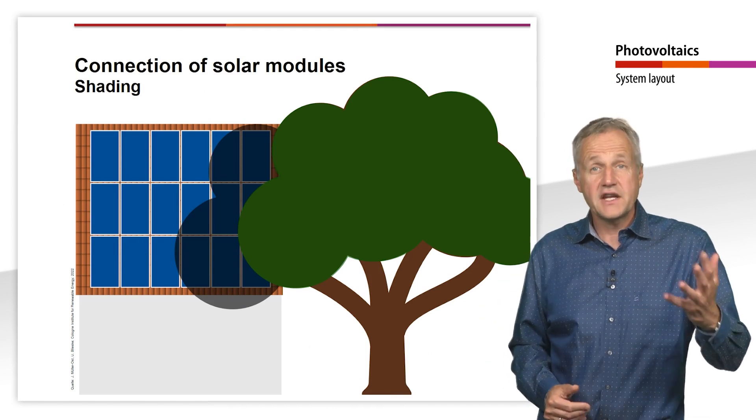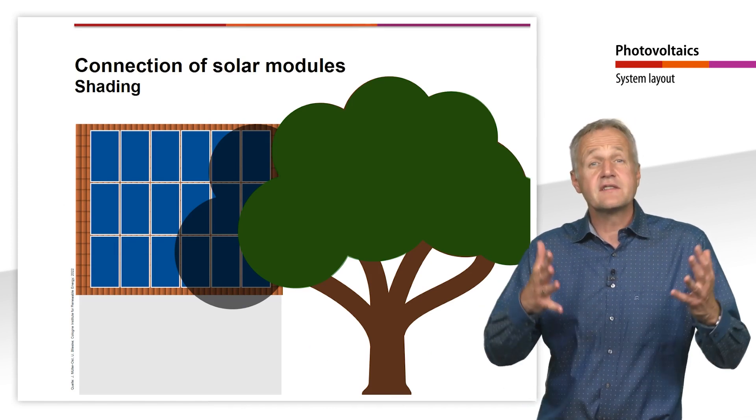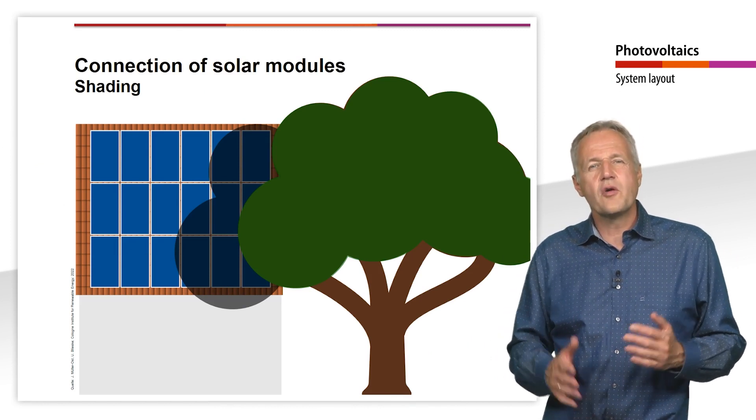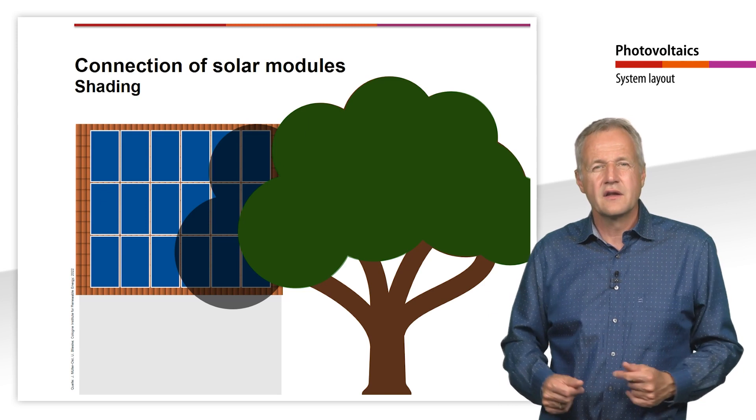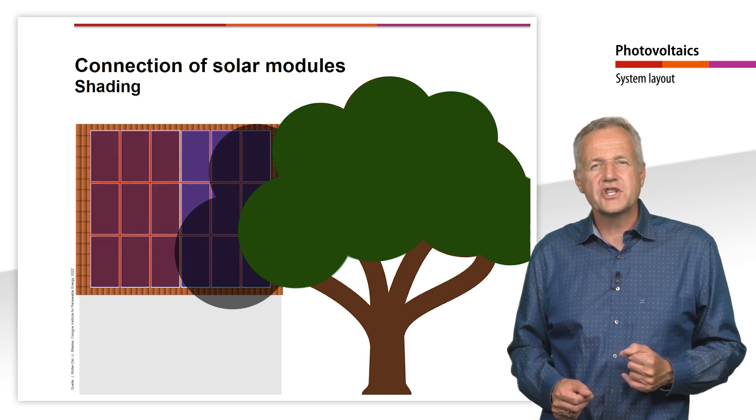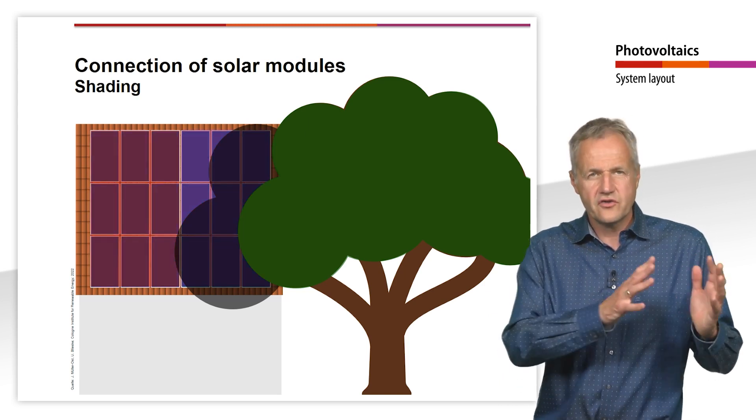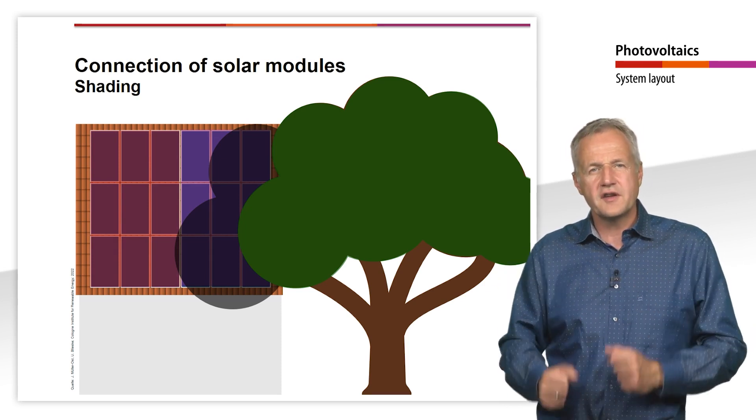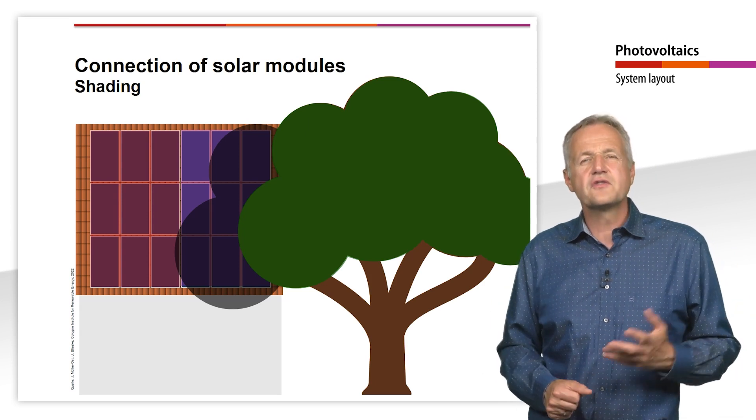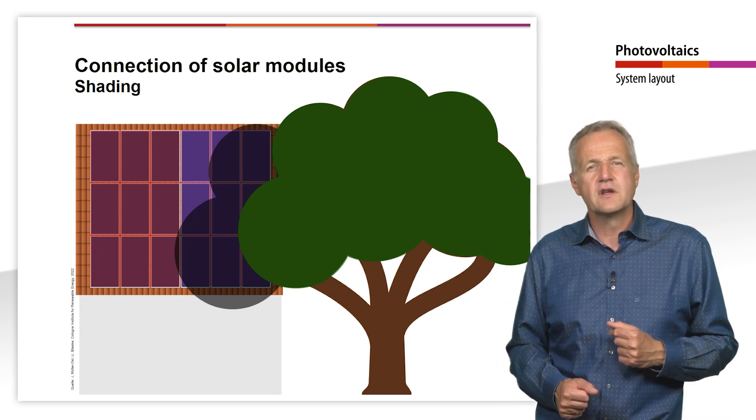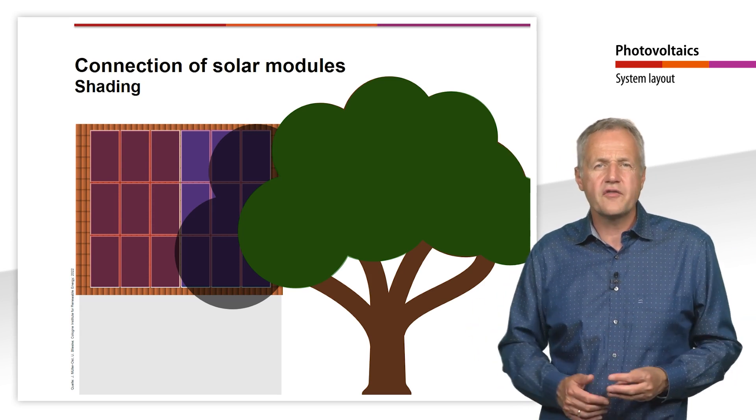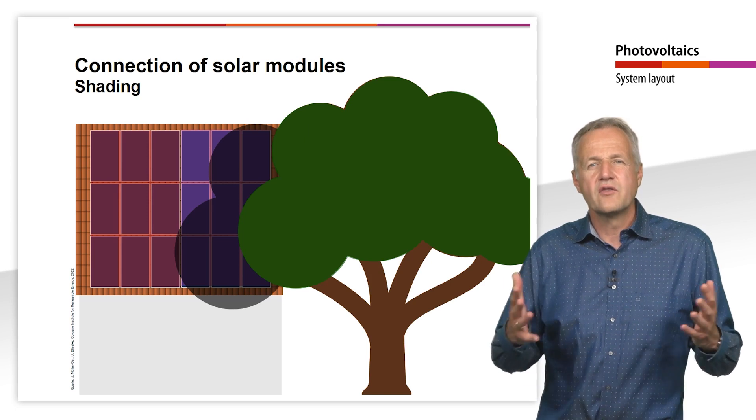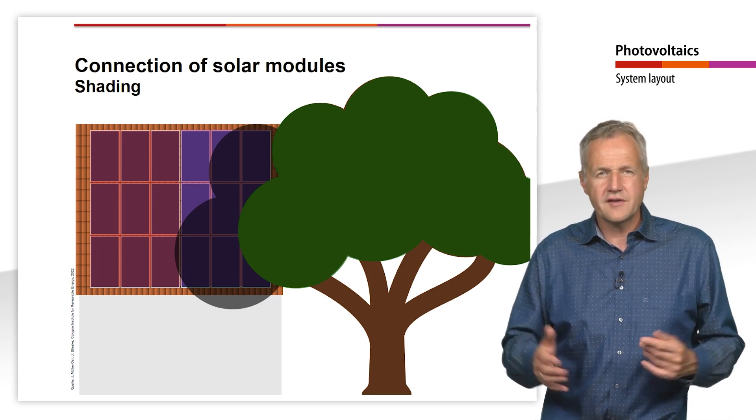The same applies to shading situations. If it is unavoidable that modules are shaded during the course of the day, these modules should be combined into one string. The permanently unshaded modules should also form a separate string. However, if the shading moves over the entire plant during the course of the day, it is often difficult to find an optimal string layout. In practice, there is a broad range of options for dealing with these interconnection problems. We will take a closer look at these in the following slides.